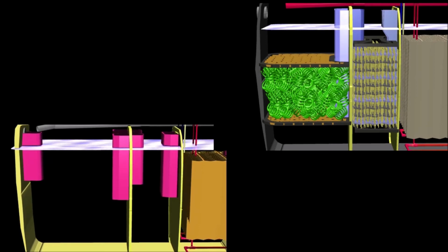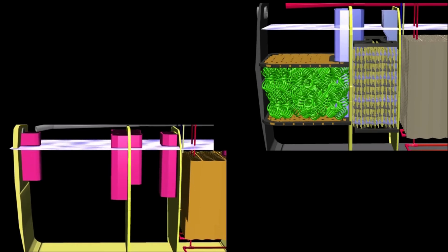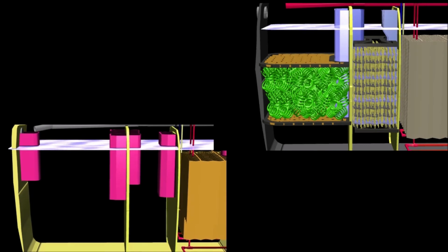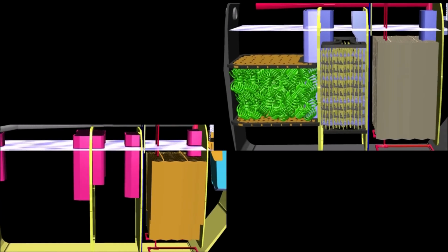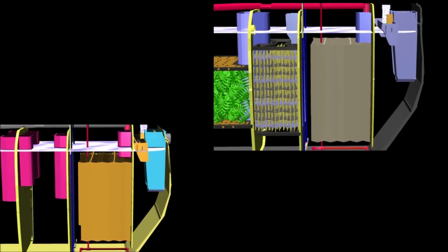At the first step, the treatment using an anaerobic filter tank is the anaerobic filter contact aeration process, and the treatment using a sedimentation separation tank is the separation contact aeration process. Both treatment methods use a contact aeration tank and a sedimentation tank for secondary treatment. And the treated wastewater is finally disinfected in a disinfection tank.